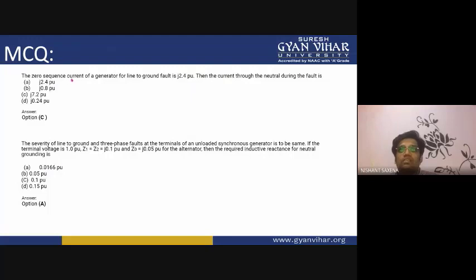Now, the zero sequence current of the generator for a line to ground fault is j2.4 per unit. Then the current through the neutral during the fault would be calculated. Calculate it, and I am giving you 2 minutes for this. Calculate the solution. It's very easy. The option is j7.2 per unit.